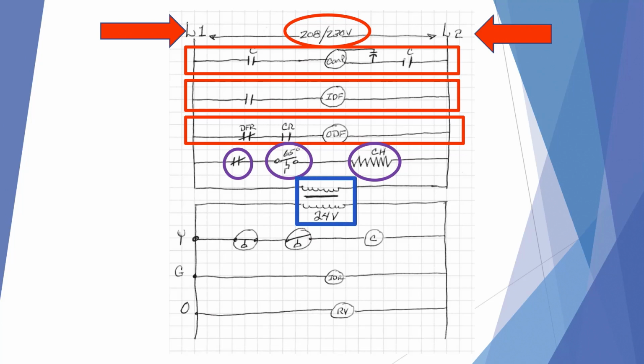We then have our transformer that is powered on the one side by the 230 volts, and it steps down the power supply to 24 volts for our control circuit. In our control circuit we have the Y circuit, which is the contactor for the compressor operation, and we also have pressure switches in this line which would either open or close on low or high pressure.